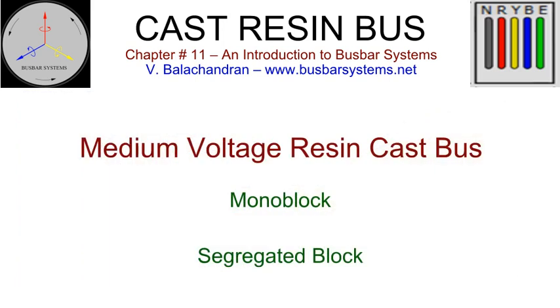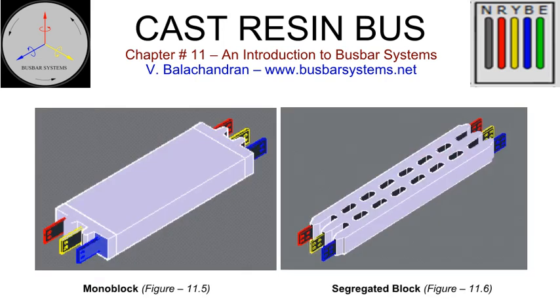Medium voltage cast resin buses are manufactured up to a current rating of 5000 amperes with copper conductors with a short time rating of 80 kA RMS for 1 second and 170 kA peak. The product is manufactured to 2 different designs depending upon the rated voltage: monoblock and segregated block. Monoblock. In monoblock design, the construction is similar to that of low voltage cast resin bus. These are manufactured for a rated voltage up to 12 kV.